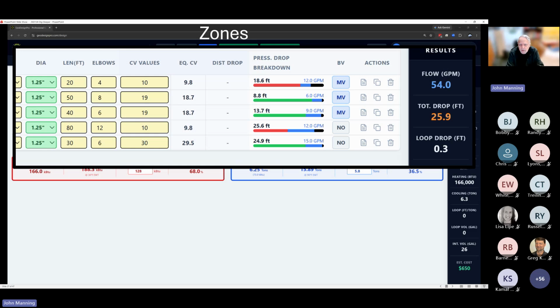to where is that pressure drop in that circuit. The first color, being red or green, is the heat pump. And you don't have any control over that. That was decided by a design engineer at the various manufacturers. But the part of the system you can control are the pipe diameters, the pipe material, the type of two-way valves, and so forth. So if the heat pump is green, that indicates that it's at least 70% of that total pressure drop, and you've done a good job reducing pressure drop on the parts you can control. If the heat pump shows up as red, then it's sort of suggesting to you that maybe your options for pipe diameter or zone valve need to be re-examined.